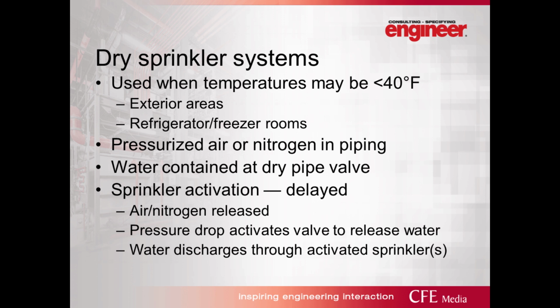Dry sprinkler systems are typically used when you can encounter freezing temperatures in the area where your system is being installed. NFPA 13 sets the temperature rating at 40 degrees Fahrenheit, so if you expect environmental conditions in the area where the sprinkler system is located to be below 40 degrees Fahrenheit, a dry system is what you want. You don't want a wet system where you have the possibility of freezing piping. Dry sprinkler systems are typically used in exterior areas, open parking garages, things like that, where the temperature can't be maintained. Obviously, this doesn't go for those areas of the country or the world where temperatures never get below 40 degrees Fahrenheit.